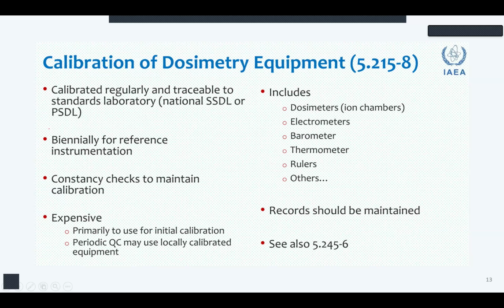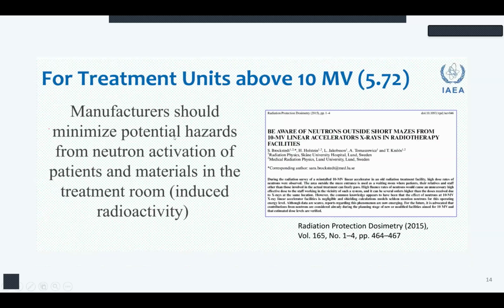And in here also, there is a mention that manufacturers should minimize potential hazards from neutron activation of patients and materials in the treatment room. In particular, we're talking about treatment linacs that exceed 10 MV. And there are publications that even at 10 MV, as you know, the use of linacs above 10 MV has reduced quite a lot worldwide due to the improvement in delivery techniques and the lack of need really for going to really high energies. But even at 10 MV, we should be careful.